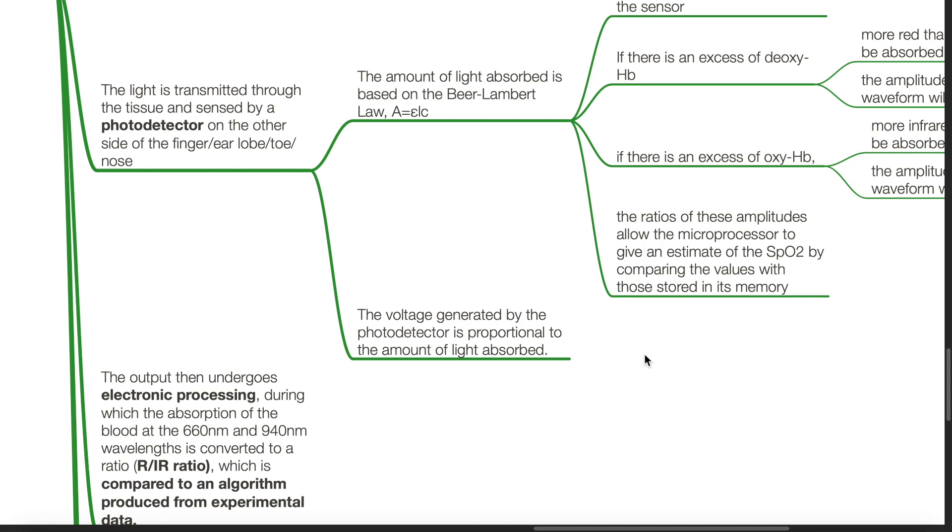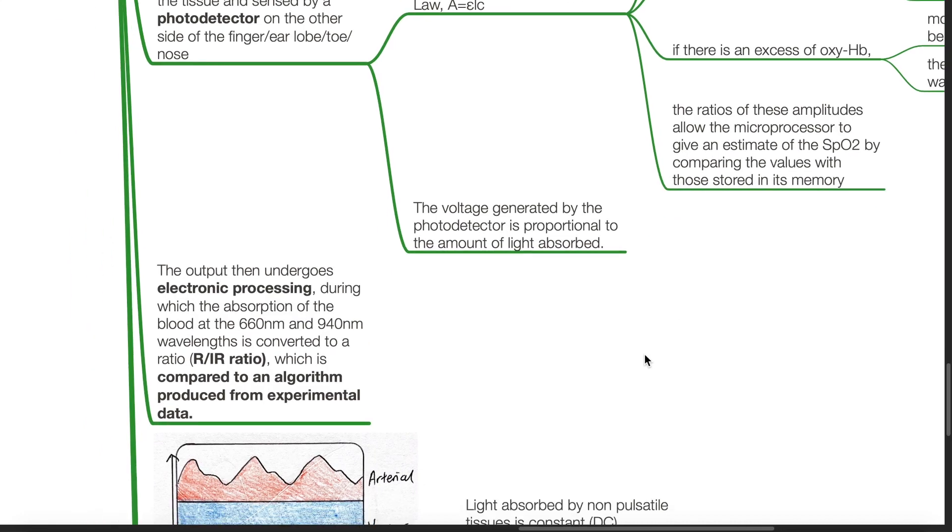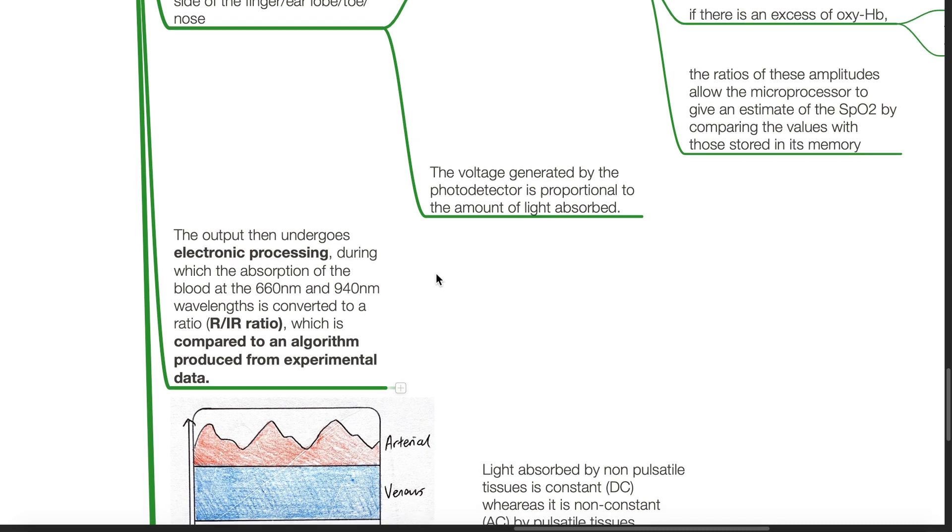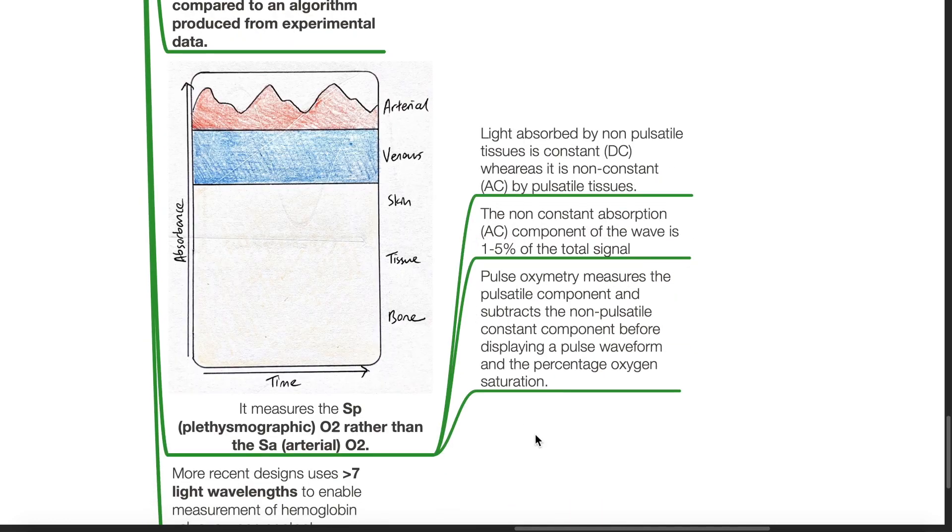The voltage generated by the photodetector is proportional to the amount of light absorbed. The output then undergoes electronic processing, during which the absorption of blood light at 660 nm and 940 nm wavelengths is converted to a ratio known as the R to IR ratio, which is compared to an algorithm produced from experimental data. It measures the plethysmographic oxygen saturation rather than the arterial oxygen saturation.